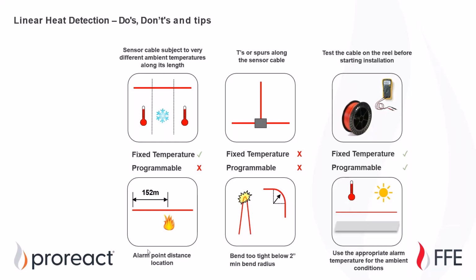Also, if you need alarm point distance location, your fixed temperature is the only one of the products that we offer that can do that. So programmable would not be a good choice in that instance, say for a road tunnel, unless you had it zoned properly for every 50-foot by 50-foot space. So T-spurs are not recommended.